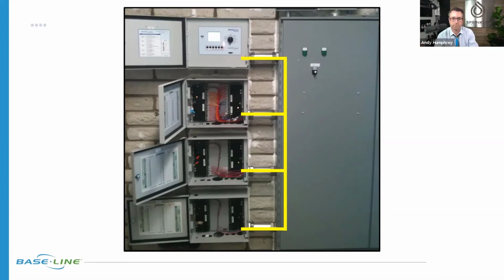That kind of lends itself well if you're replacing multiple controllers in close proximity, but not right next to each other. There's no need to move all the physical wires — you could just put 48 zones on a 2-wire path and bring them back into the controller. So that's one way to look at it.